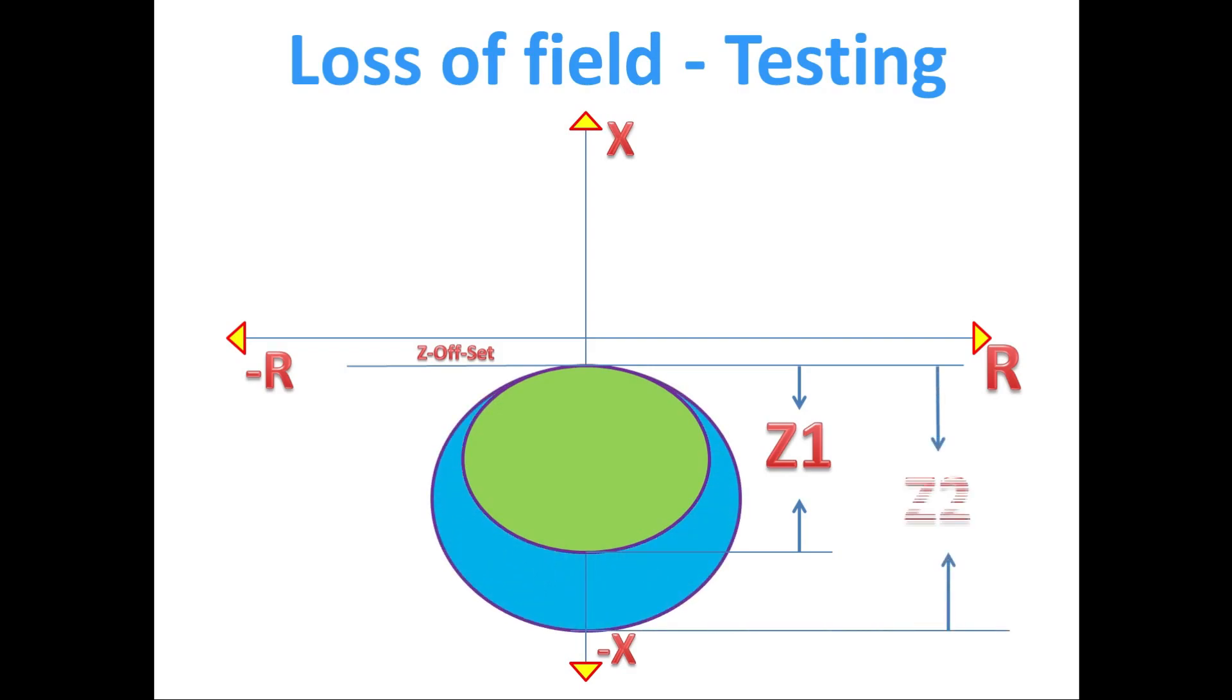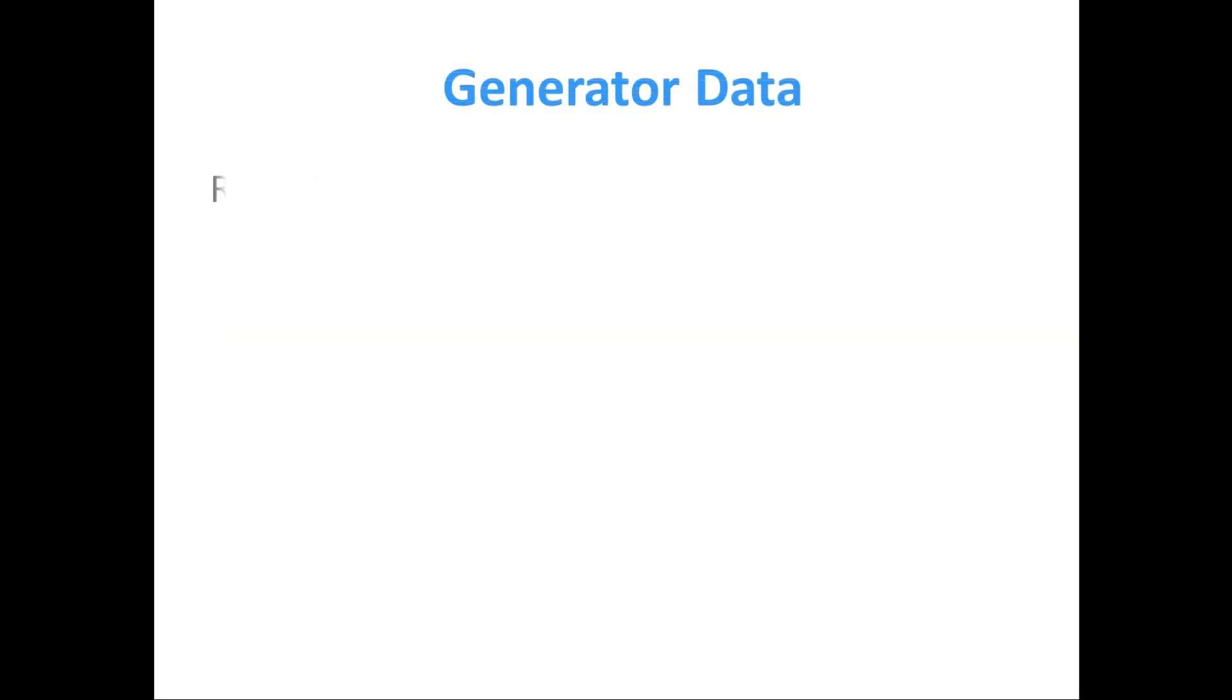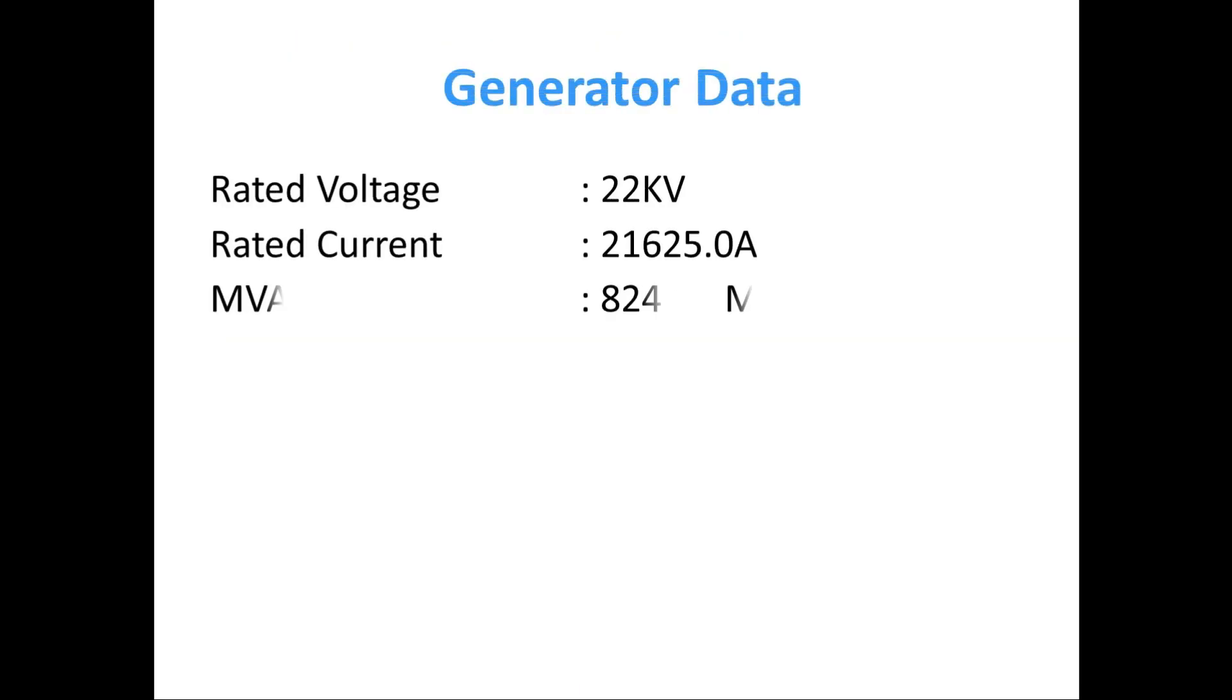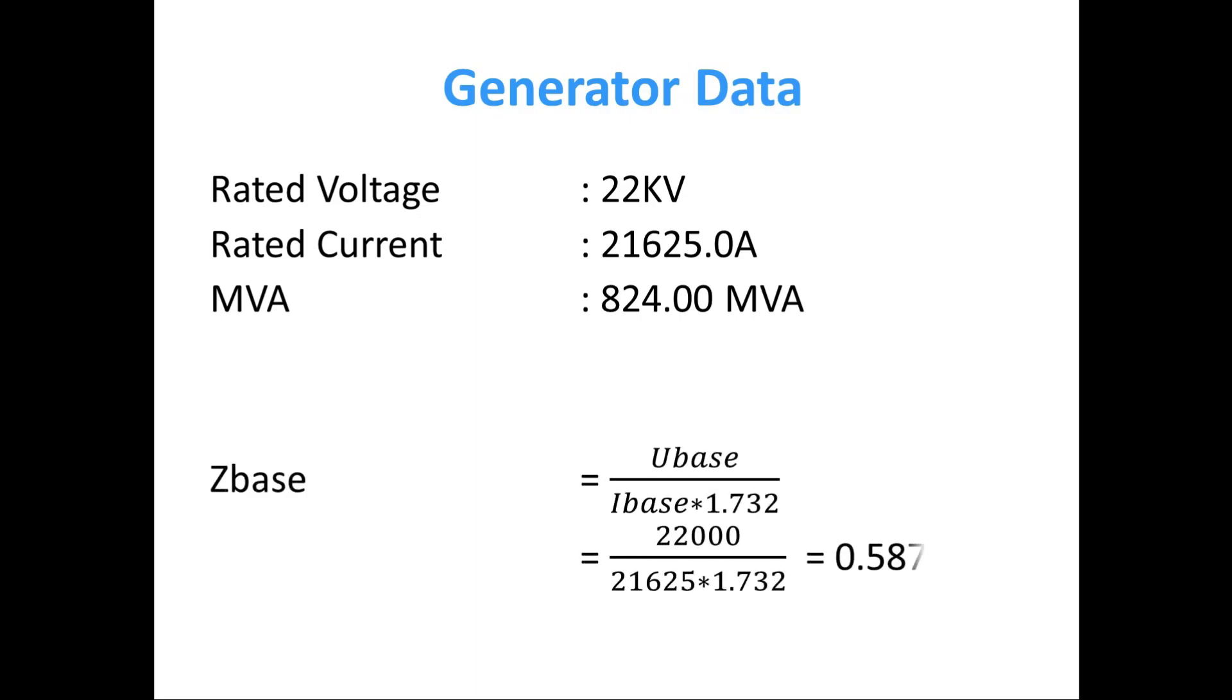This is the reference diagram. Before going into calculation, first we have to see the generator nameplate detail. Let us consider the generator is 22 kV rated voltage and rated current is 21,625 amps. For this, first we have to calculate the Z base, which is equal to U base divided by I base into 1.732, which gives 0.587.